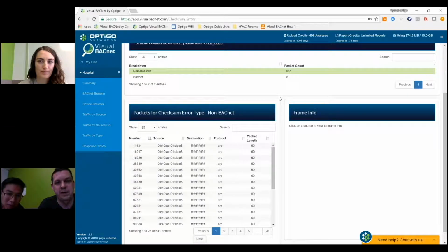Sometimes it could be the sign of a loose connection. And this is always coming from the same source, all coming from the exact same location. It's obviously broadcasting out, but it could be an indication of something happening on the site. You could either go and try to re-terminate the connections or just keep an eye on it to see if it gets worse.